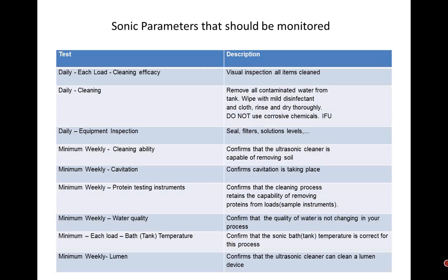Because remember, if there's no cavitation and you're just running a 15-minute tank empty, that's like soaking an instrument for 15 minutes in enzymatic solution. So again, you want to make sure there's cleaning activity and cavitation.